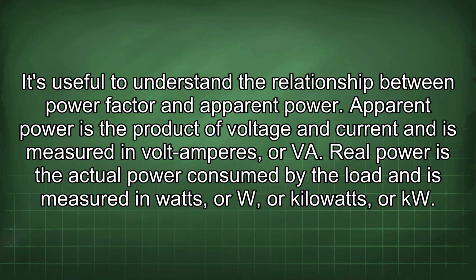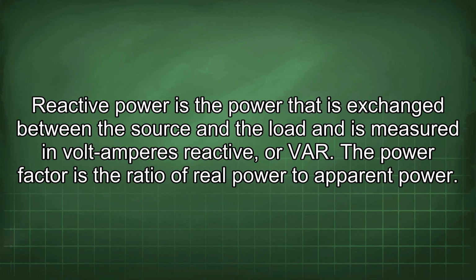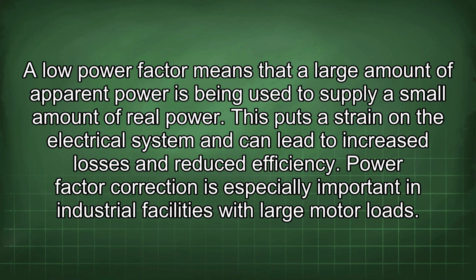It's useful to understand the relationship between power factor and apparent power. Apparent power is the product of voltage and current and is measured in volt amperes or VA. Real power is the actual power consumed by the load and is measured in watts or W or kilowatts or kW. Reactive power is the power that is exchanged between the source and the load and is measured in volt amperes reactive or var. The power factor is the ratio of real power to apparent power. A low power factor means that a large amount of apparent power is being used to supply a small amount of real power. This puts a strain on the electrical system and can lead to increased losses and reduced efficiency.